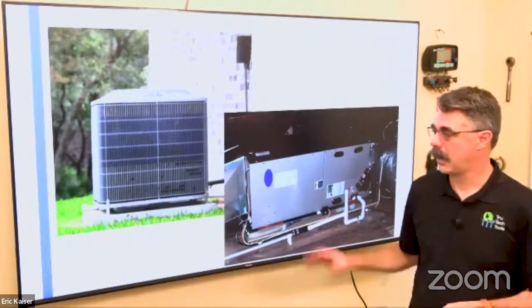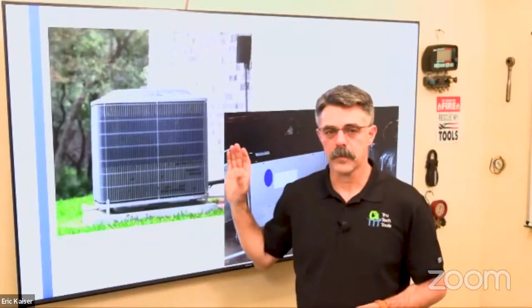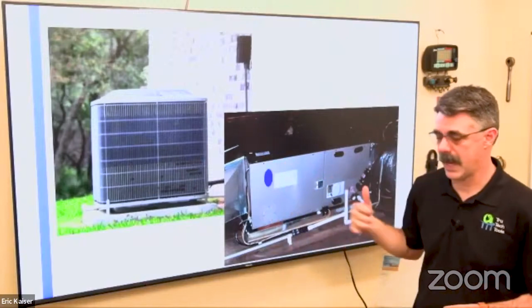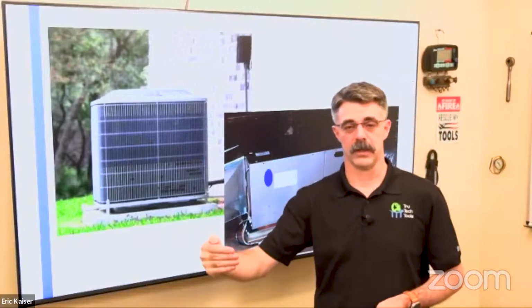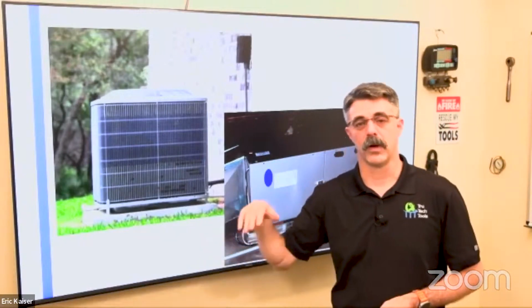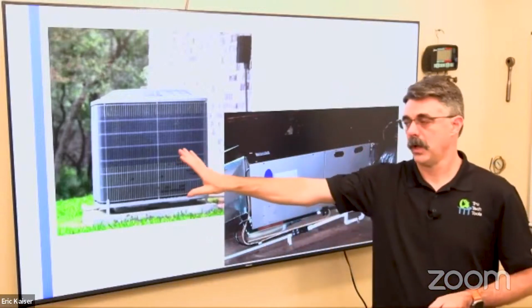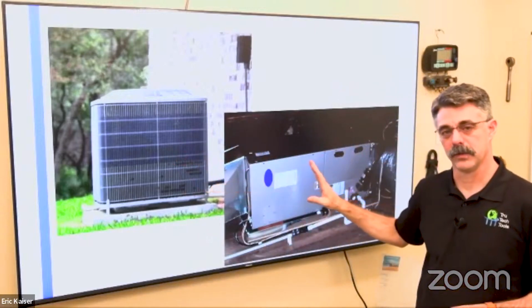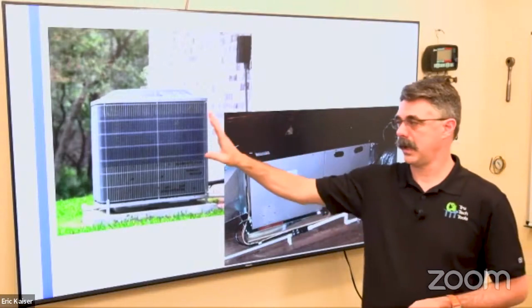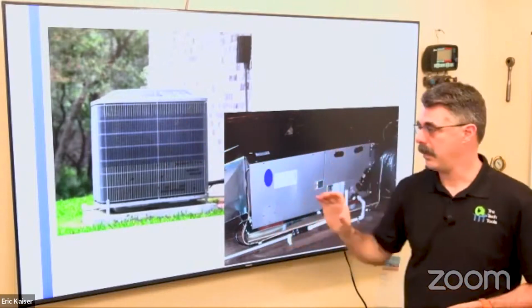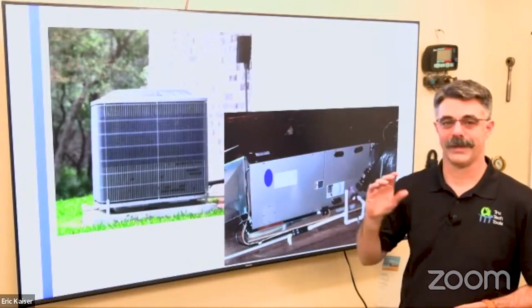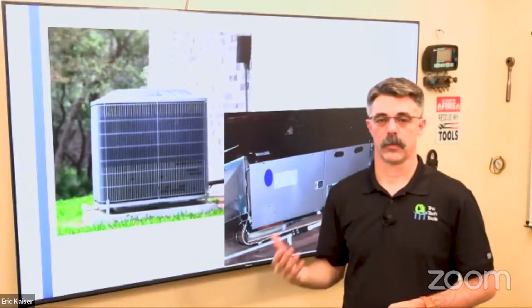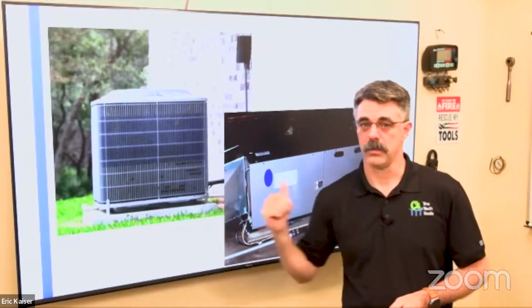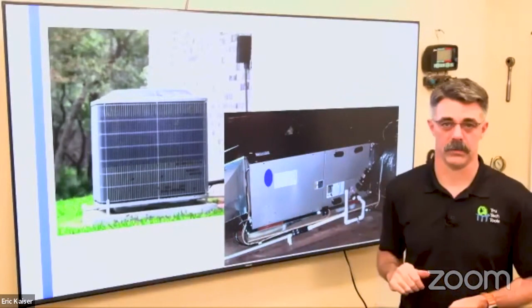All right. Now we need to select the equipment. The equipment needs to match. And when we say match, not only does it need to match the conditions that the house needs, but it also needs to match each other, because when we're talking about a system, most of the time we're going to have an indoor air handler and an outdoor heat pump. And those two need to be able to work together. And there are rating systems for that, of course, from AHRI and things like that. And if those two don't work together, well, then you may not get the capacity that you think you're going to get out of it.